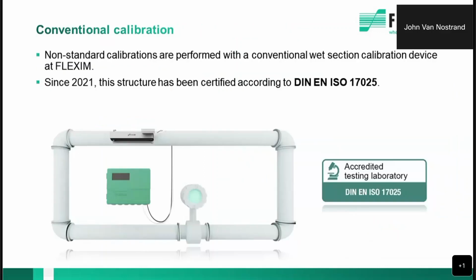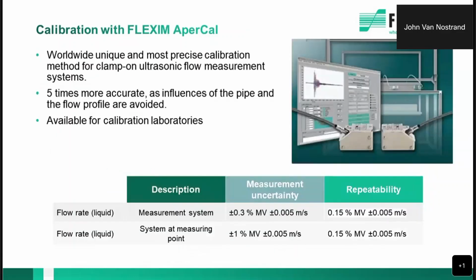So our calibration rig at the factory in New York can use one of two methods for calibration: the conventional method, using a master meter in comparison with water in a flow loop to compare the device under test to a standard meter. And then there's also a method called the AperCal calibration method, and that's a new calibration method that is used for ultrasonics.